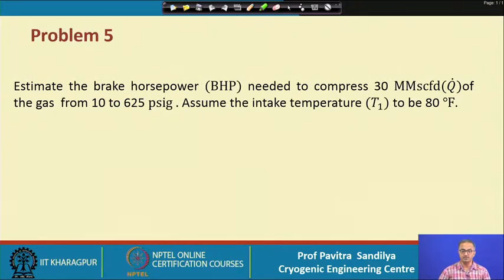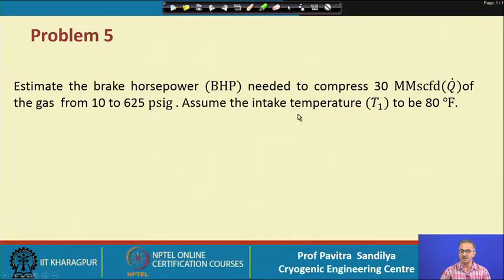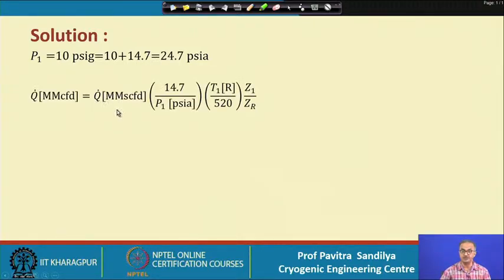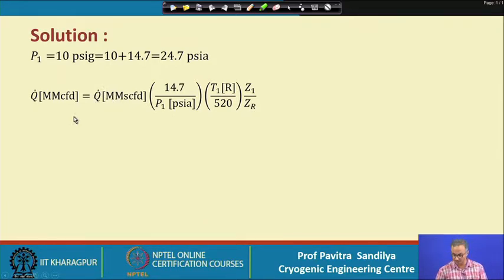In the next problem, we have to find the brake horsepower needed to compress a given amount of gas from 10 to 625 psig, with an intake temperature of 80°F. We first convert gauge pressures to absolute pressures by adding 14.7 psi. Then we use the expression learned earlier to find the actual volumetric flow rate from the standard flow rate.